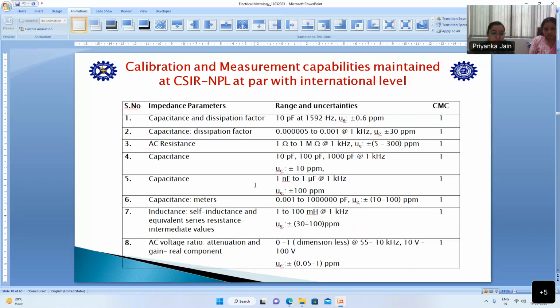Next are other parameters, capacitance and dissipation factor. These come under impedance metrology. The capacitance value is 10 picofarad at 1592 hertz frequency and the uncertainty is 0.6 ppm. For capacitance dissipation factor, we have 0.5 times 10^-5 to 0.001 at 1 kilohertz. The uncertainty is 30 ppm. Next is AC resistance. The AC resistance uncertainty is derived from the DC resistance. The value is from 1 ohm to 1 megaohm at 1 kilohertz. The uncertainty is 5 to 300 ppm. Next is capacitance of 10 picofarad, 100 picofarad, 1000 picofarad at 1 kilohertz. The uncertainty is plus or minus 10 ppm. Another capacitance range is from 1 nanofarad to 1 microfarad at 1 kilohertz. The uncertainty is plus or minus 100 ppm.